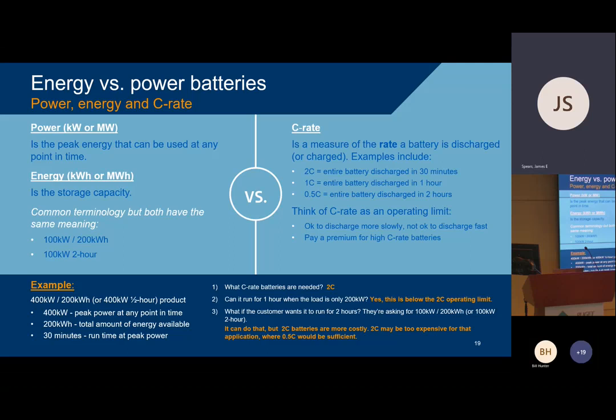An energy battery is more optimized towards the long, slow discharges with the emphasis on long. So a 2C battery is going to be rated to discharge its entire capacity in 30 minutes. A 1C battery is going to discharge the entire battery in 1 hour. A 0.5C battery means the battery is rated to be discharged over 2 hours. Can I simply buy a 5C battery and use it for any of these applications? Yes, but the high C battery is going to be much too expensive and require many more battery cabinets, for example, if my application only calls for 1C or a 1 hour discharge.